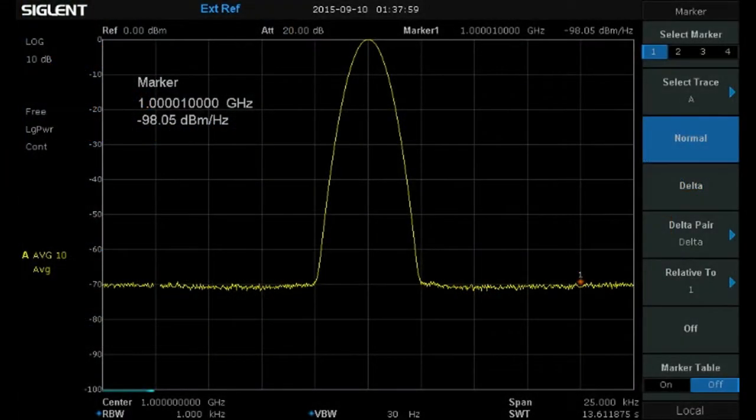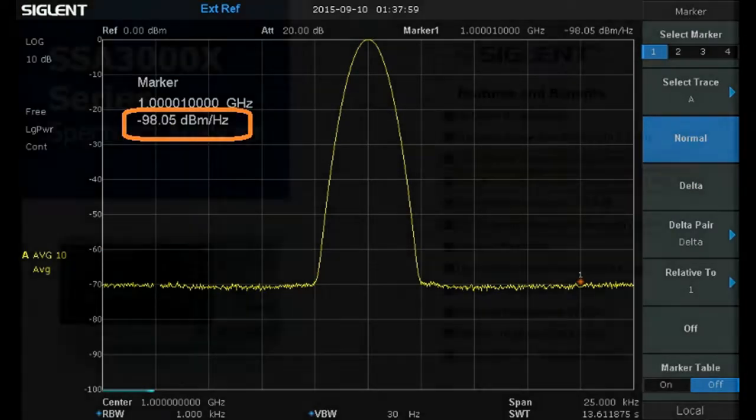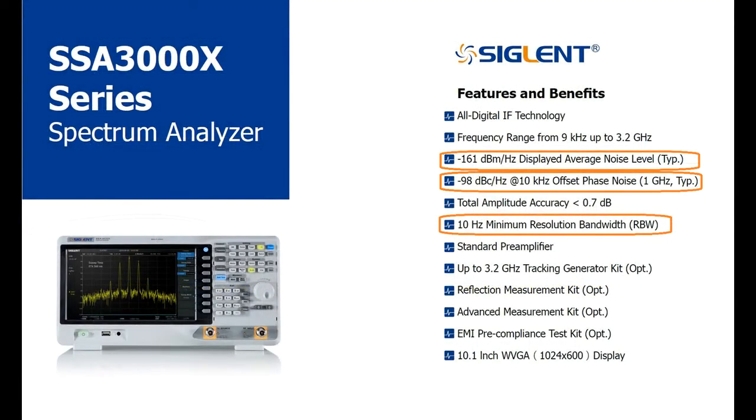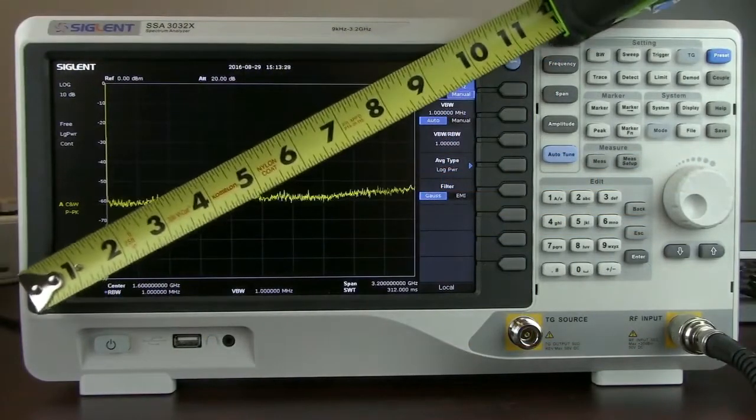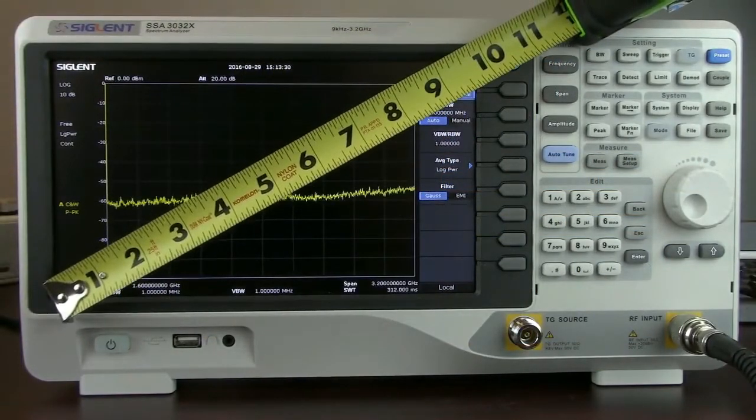The SSA 3000X delivers with respectable phase noise of minus 98 dBc per hertz at a 10 kHz offset. The SSA 3000X also features a 10 inch WVGA display and it does measure a full 10 inches or 10.1 and we've got about 7 inches of actual trace area.